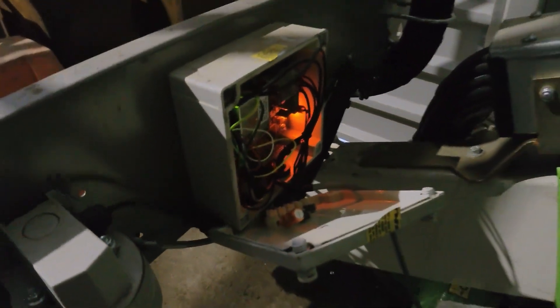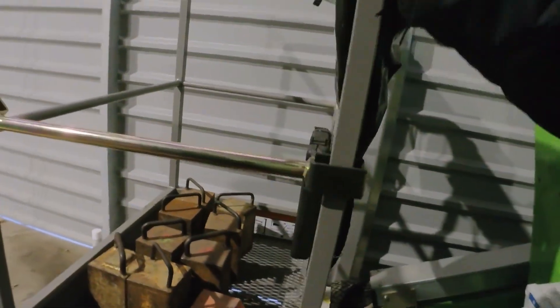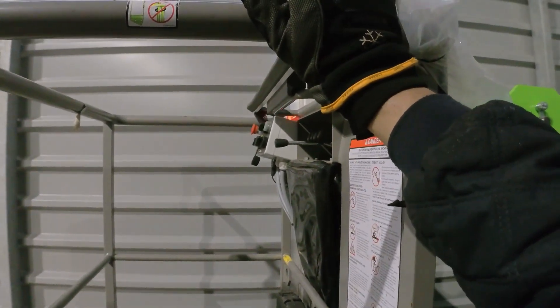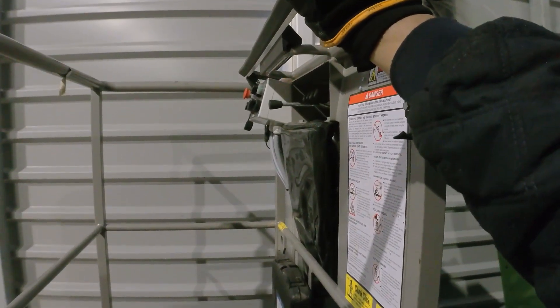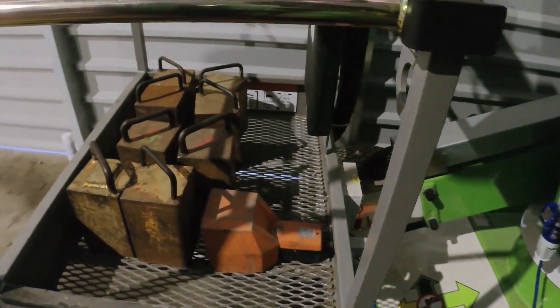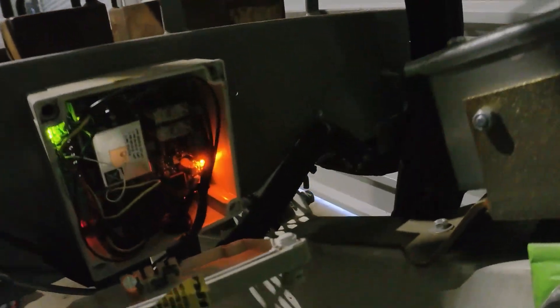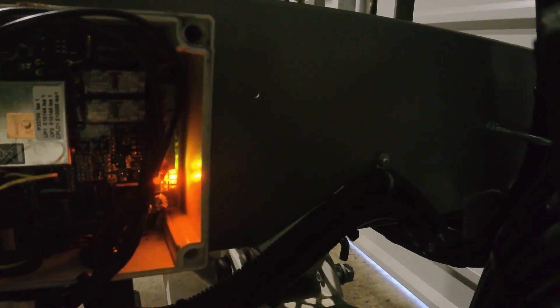It's alarming now again because it's overloaded. So if I disconnect this plug here, my calibration tool, what I will do is just gently push the cage up. So the alarm stopped. If I let it go, the alarm starts again. And you can see on the red light, so once I pull the cage up, the red light starts flashing.